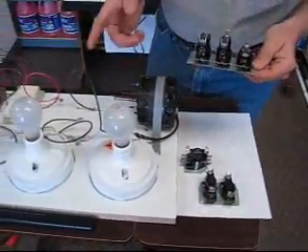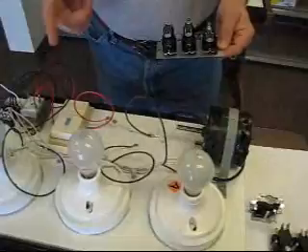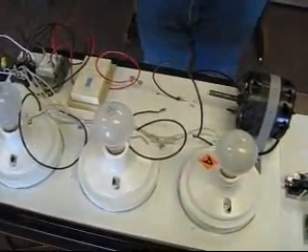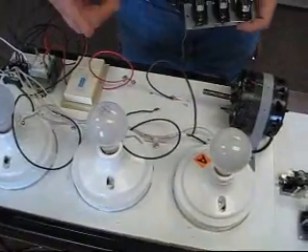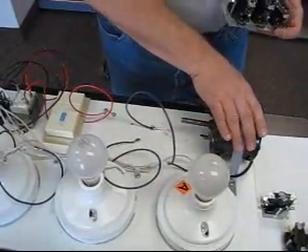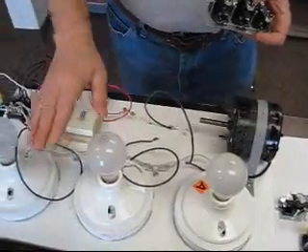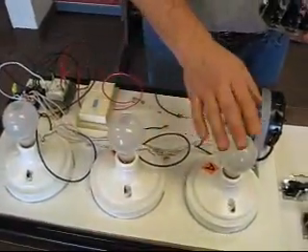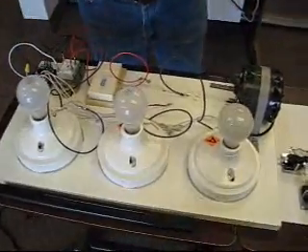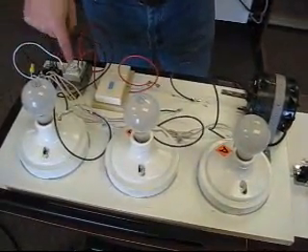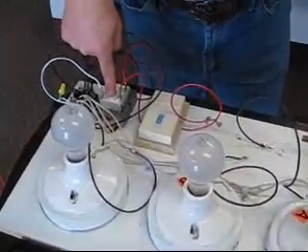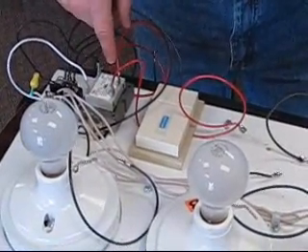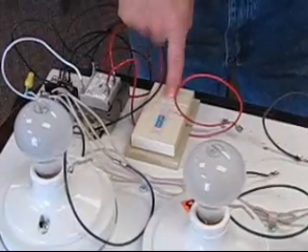So what we're going to do is hook a sequencer into our little tester here just to show you how they work. In our tester, we have a motor which acts as the blower motor for your furnace. Each light will be a heating element. So pretend those are heating elements. Then we've got our power supply. We have our transformer. What the transformer does is it reduces the 120 volts to 24 volts. And then you have your thermostat.